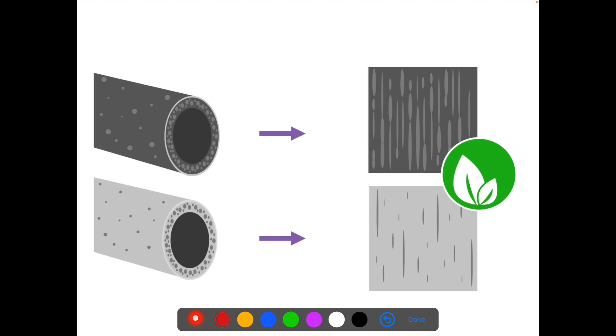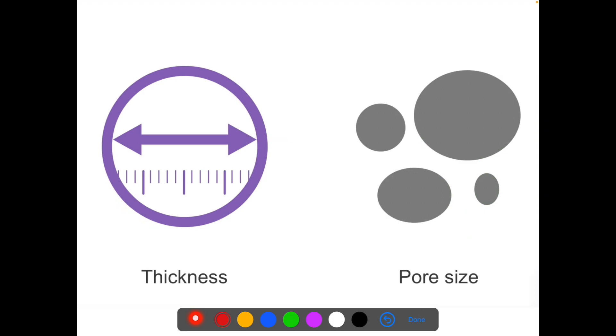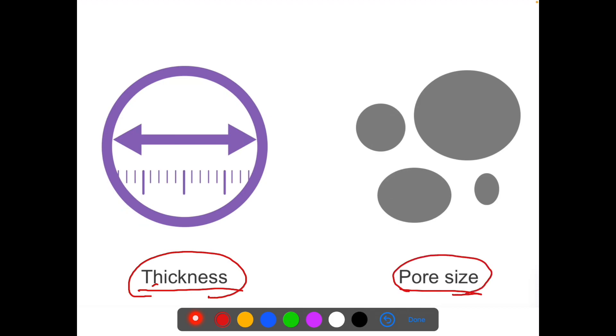The permeability of these membranes depends on two factors: the thickness of the membrane and the pore size. The internal diameter of the hollow fibers is 180 to 200 microns and the wall thickness is 30 to 40 microns. The thickness of the membrane wall and the pore size present in the membranes dictate the permeability of the dialyser.